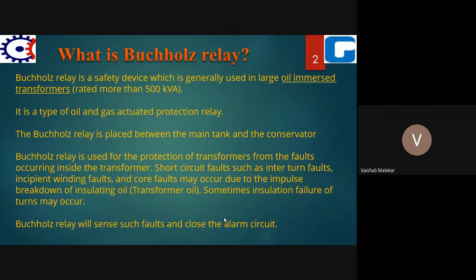Such faults are short circuit faults, which may be inter-turn faults in the winding, incipient winding faults, and core faults, and these may be due to impulse breakdown of the insulating oil. This relay will protect the transformer from such faults. Sometimes insulation failure of turns may also occur, means the windings have insulation, and sometimes the winding insulation may break and a fault occurs. The Buchholz relay in the transformer will protect it from such faults.